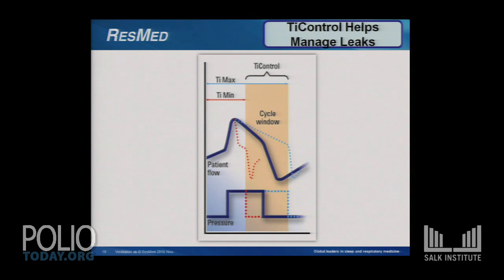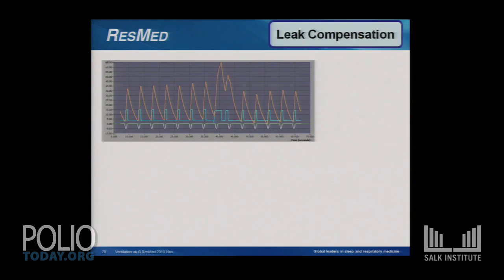What it is, we can set a minimum time for the breath and a maximum time for the breath. So normally you inhale and exhale as you like, what's comfortable for you. However, if you try to have a very, very short breath, that might not be enough time for adequate gas exchange. So we can say the breath has to last at least this long, but no longer than this. So I call it putting brackets around the breath. Somewhere in the middle, the patient can cycle the breath. So let me show you what happens, why it's so important.